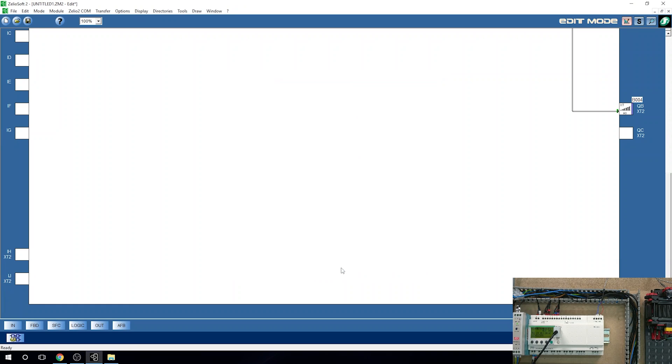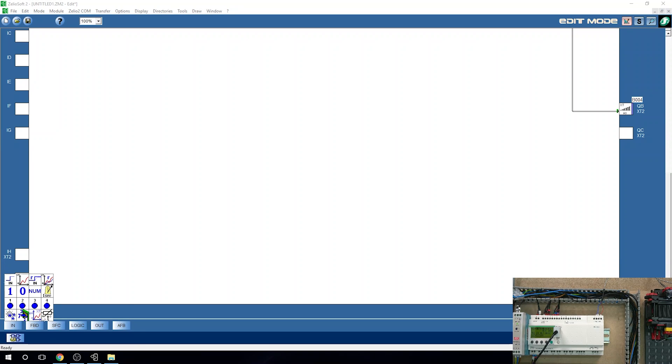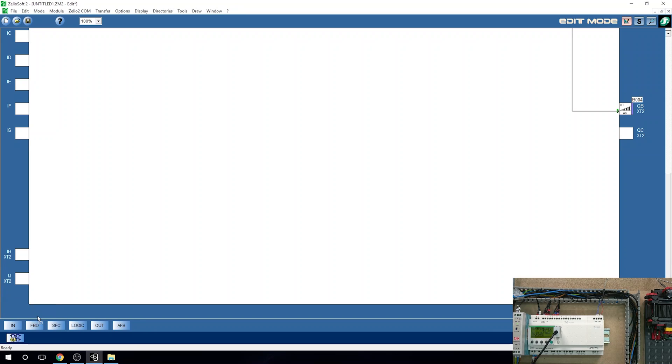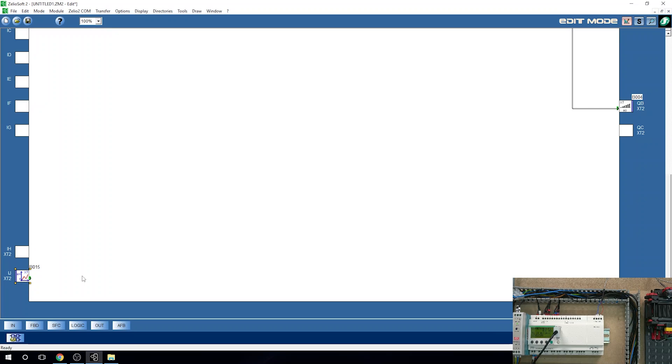From there on, going to inputs and grab the one that says XT. It pretty much represents the XT card. You hold that one and then put it into the IJ. This is where the PT100 signal is coming in from our temperature probe. What I'm going to do now is load this into the controller and quickly show you the initial reading.